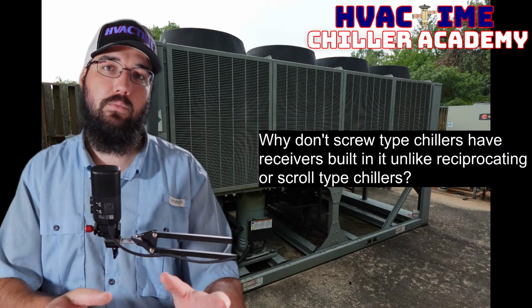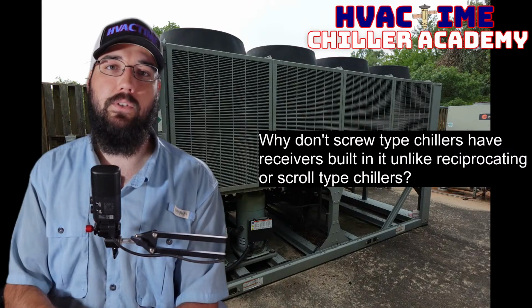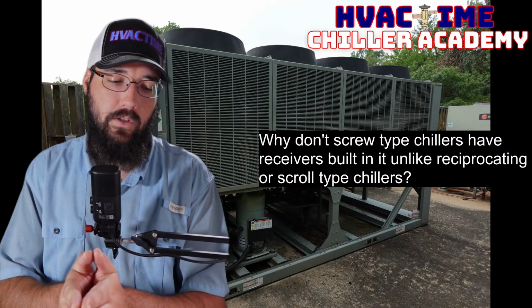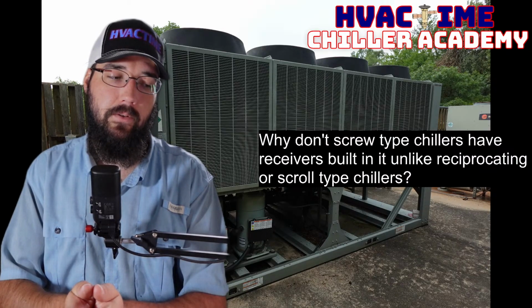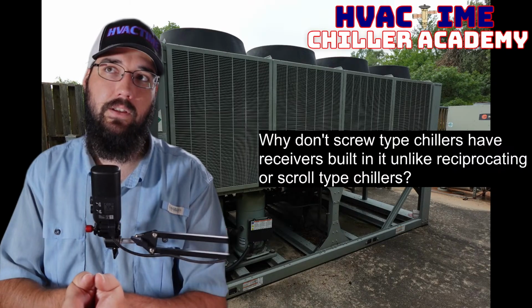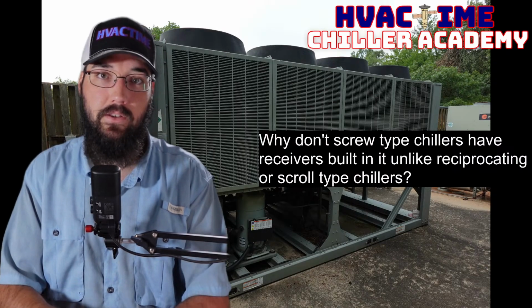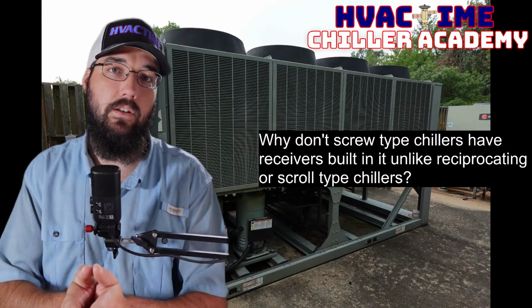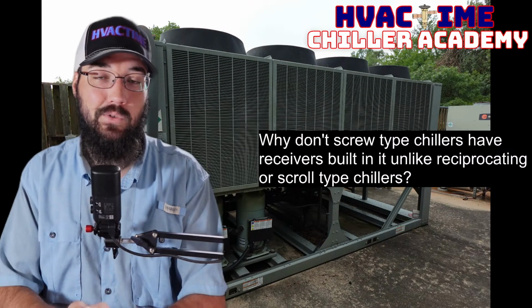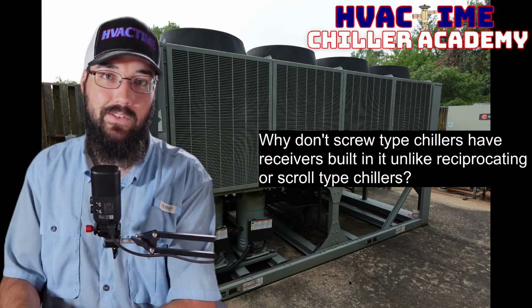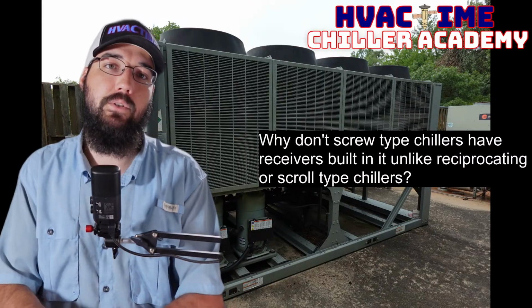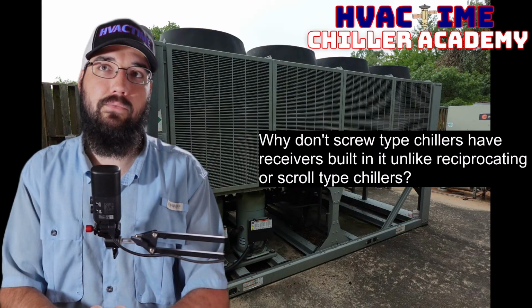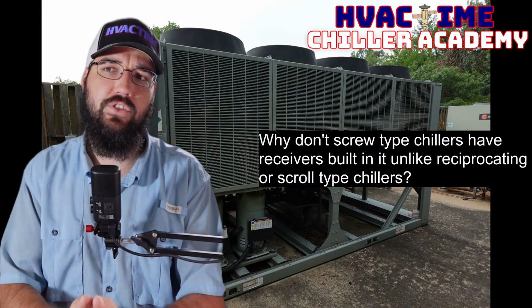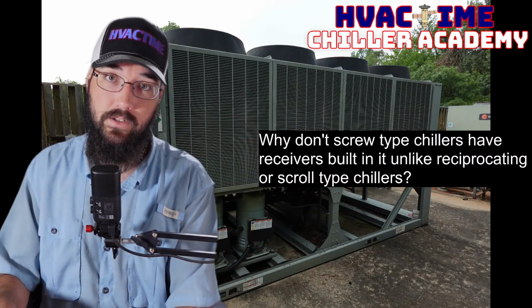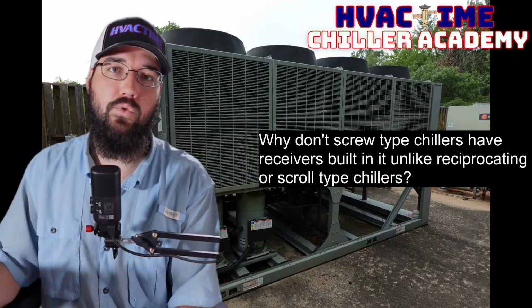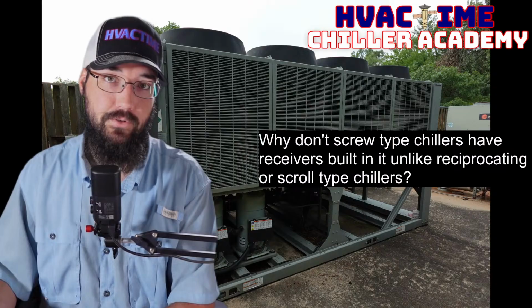So let's get into my thoughts on where the liquid line receiver comes into play in the first place. The liquid line receiver is there to give the refrigerant space as the load demands heavily fluctuate. This is why we see liquid line receivers in low temp refrigeration. There can be extreme swings from not only box load but seasonal swings, where the amount of refrigerant we need to push through can vary heavily. So much so that just stacking it in the condenser, especially a very small condenser, is not sufficient. There's not enough room to stack that much without causing head pressure issues as well.